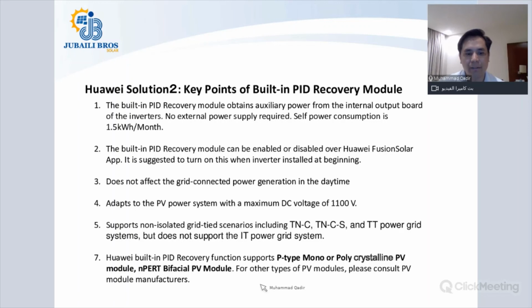Huawei's built-in PID recovery function supports the P-type mono or polycrystalline PV modules and nPERT bifacial PV modules. For other types of PV modules, if you're using them in your PV plant, you can consult us as well, and we can cross-confirm again if it's possible to use the PID recovery or the NT-PID feature to cure the effect.